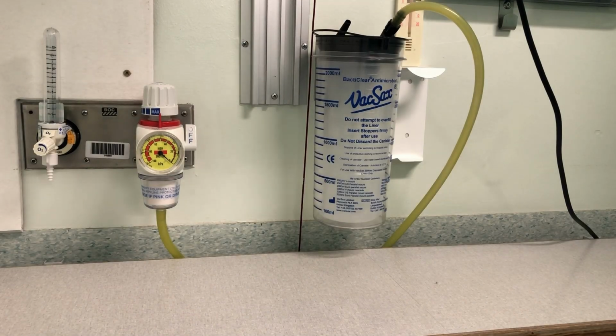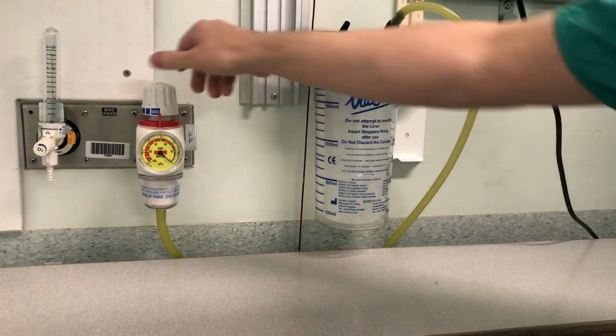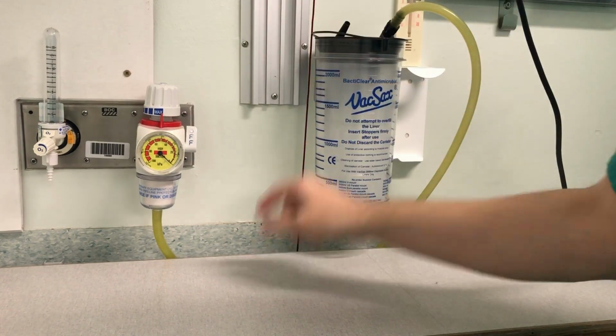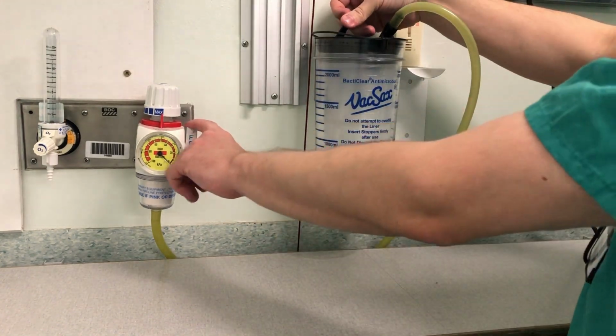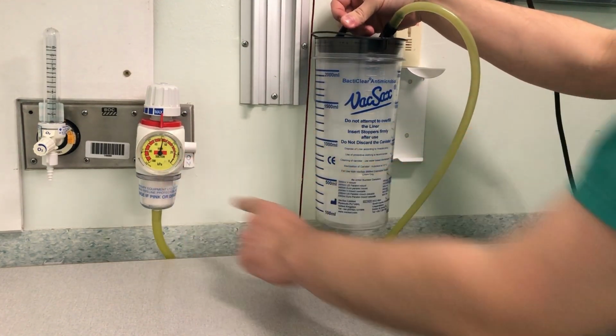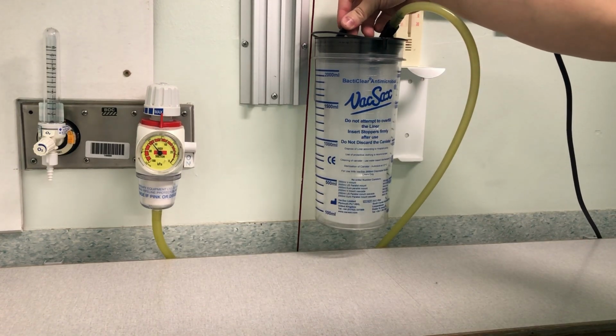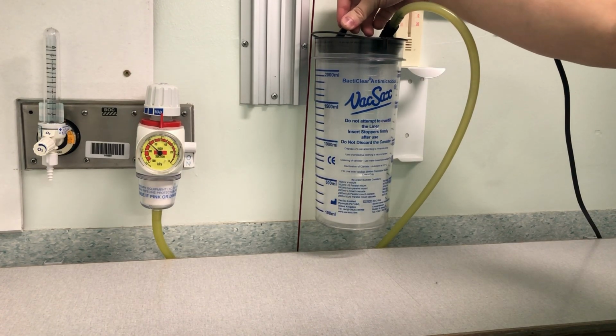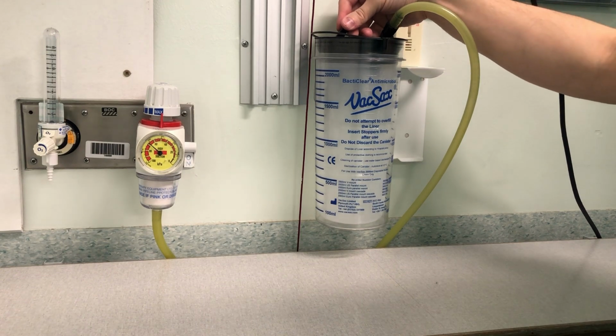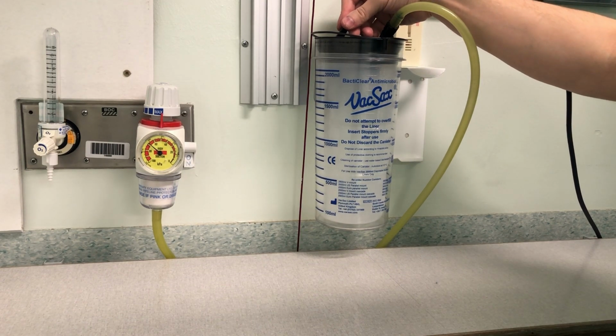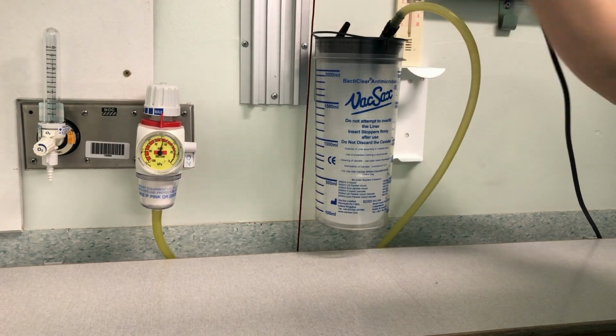But always check that the Vacsax liner is working. Conduct a pre-use check: turn on the vacuum to maximum and place your finger over the patient port located on the lid of the liner, ensuring a vacuum is present. Vacuum will build up when all parts are assembled correctly. Confirm that the suction is present at the patient tube by manually occluding the patient suction tube before proceeding.